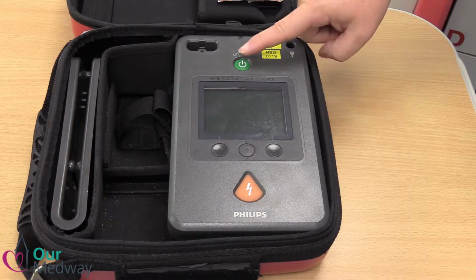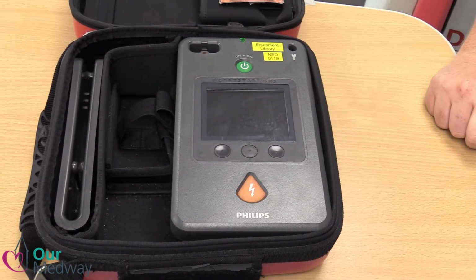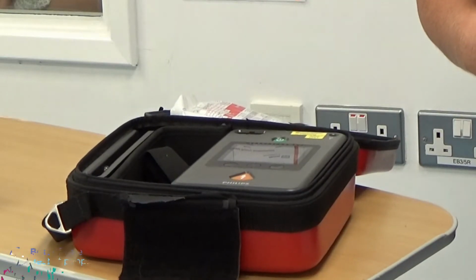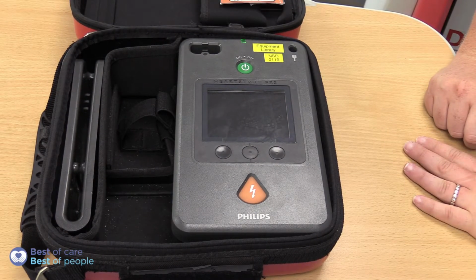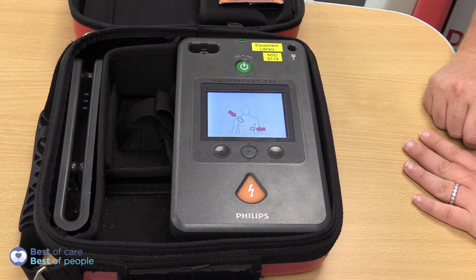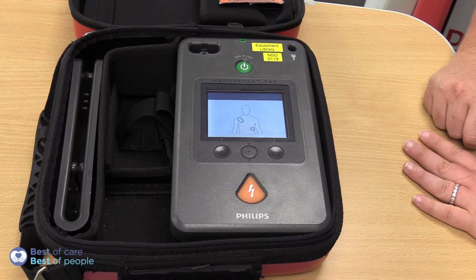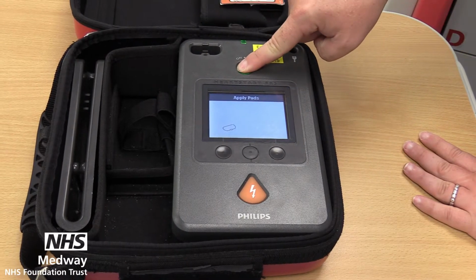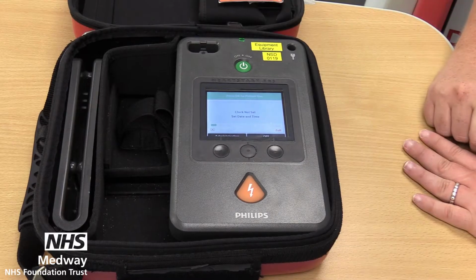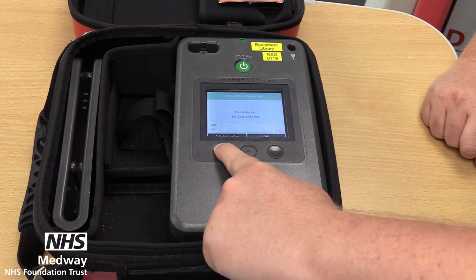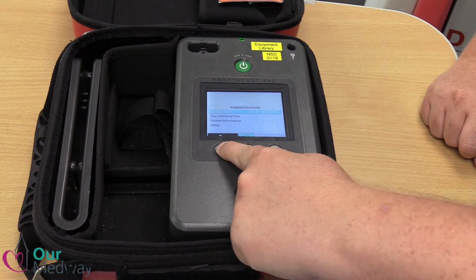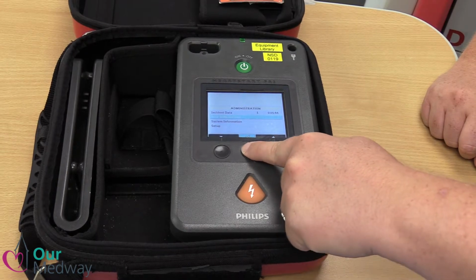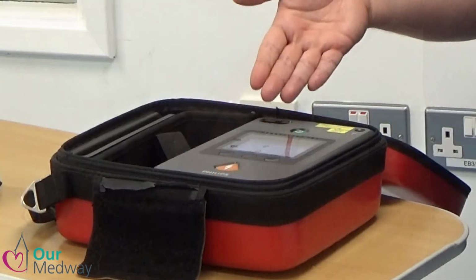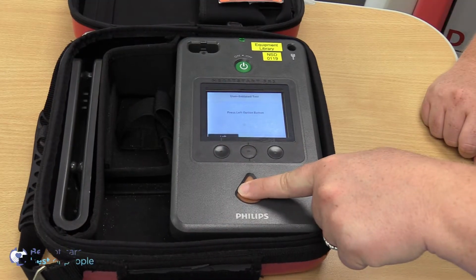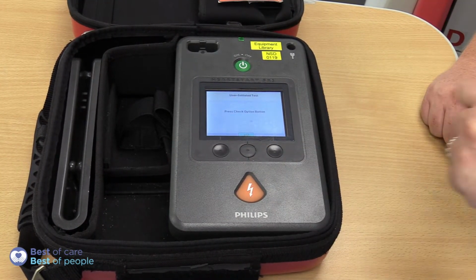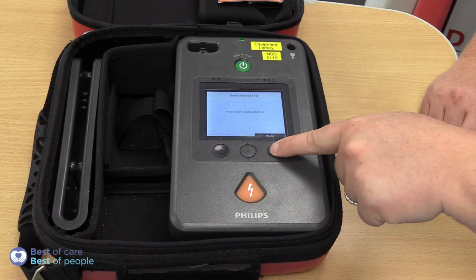In order to carry out your test, I want you to turn your defibrillator on as if you're going to use it. Once the defibrillator starts to talk to you and give you instructions as it normally would, I want you to press the on button again. Apply pad. This will then give you two options at the bottom of the screen, one that will say test. Push the soft test key at the bottom left-hand corner, and then the defib will talk you through what it wants you to do. So for example, now it's asking me to push the shock button. It's then asking me to push the left, centre and right, and so on.